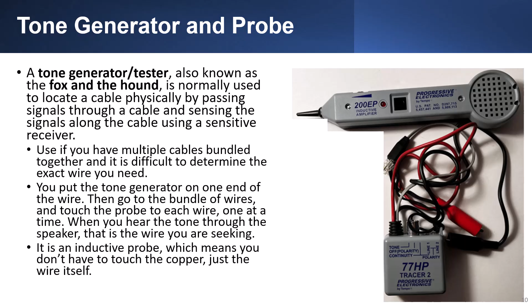A tone generator or tester, also known as the fox and the hound, is normally used to locate a cable physically by passing signals through a cable and sensing the signals along the cable using a sensitive receiver. You use it if you have multiple cables bundled together and it's difficult to determine the exact wire you need. You put the tone generator on one end of the wire, then go to the bundle of wires and touch the probe to each wire one at a time. When you hear the tone through the speaker, that is the wire you are seeking. It is an inductive probe, which means you don't have to touch the copper, just the wire itself.